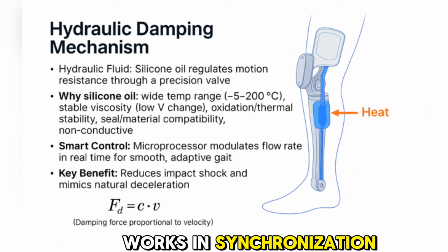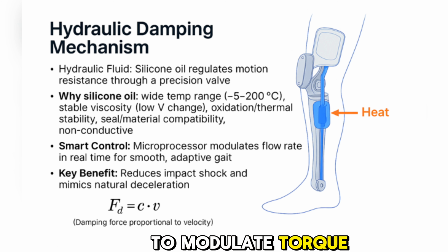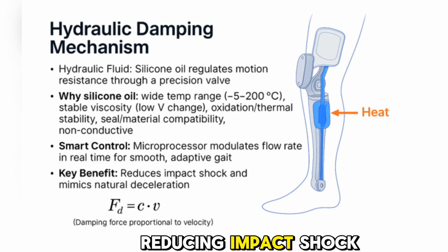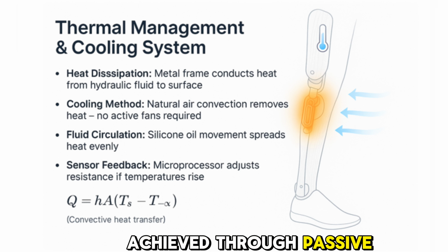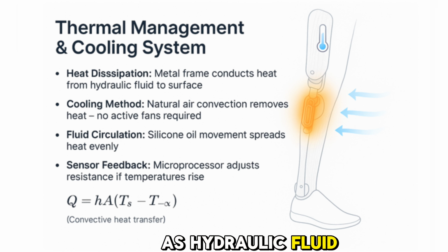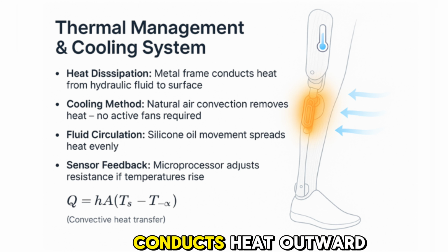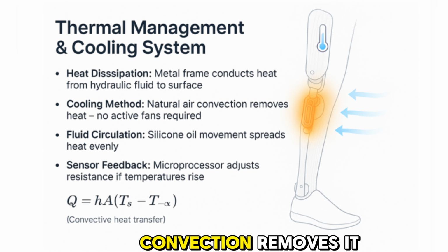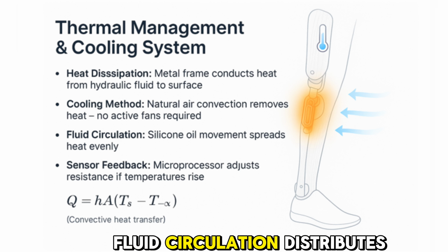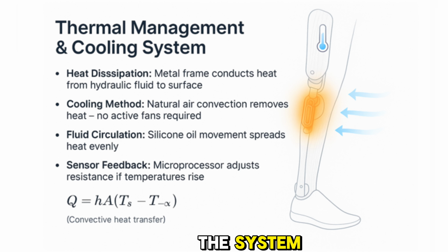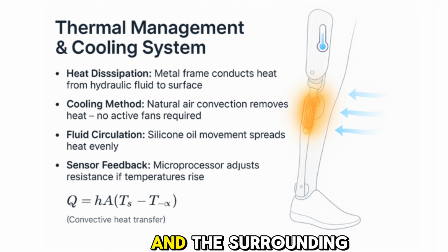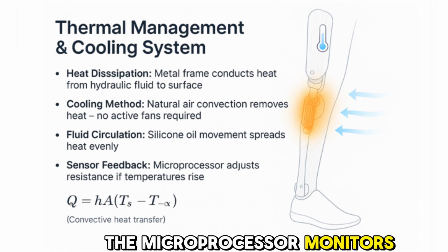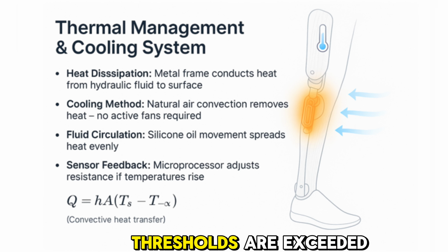The hydraulic unit works in synchronization with the microprocessor to modulate torque precisely during stance and swing, reducing impact shock. Thermal management is achieved through passive conduction and convection. As hydraulic fluid moves through the damping unit, kinetic energy is converted into heat. The metal frame conducts heat outward, while natural air convection removes it from the surface. Fluid circulation distributes heat evenly within the system. The heat transfer rate is determined by multiplying the convection heat transfer coefficient by the surface area and the temperature difference between the device surface and the surrounding air. The microprocessor monitors thermal conditions and adjusts resistance if thresholds are exceeded.